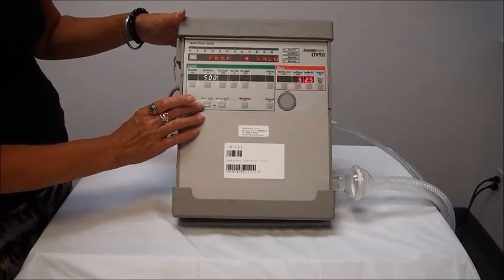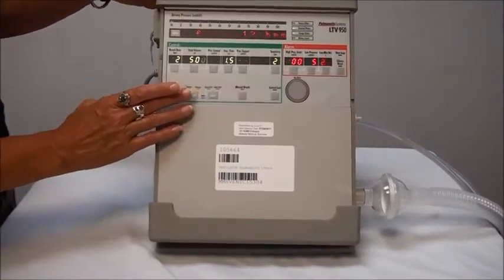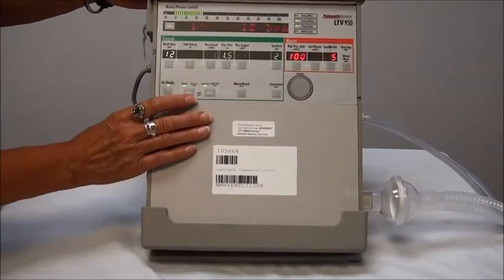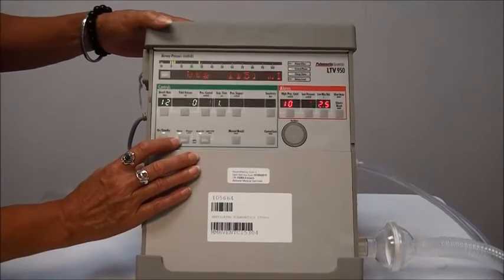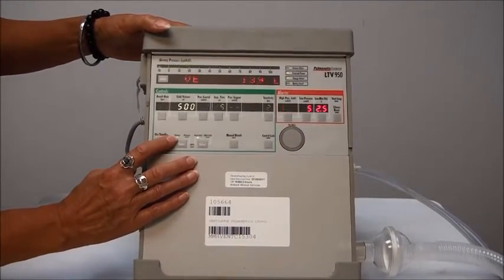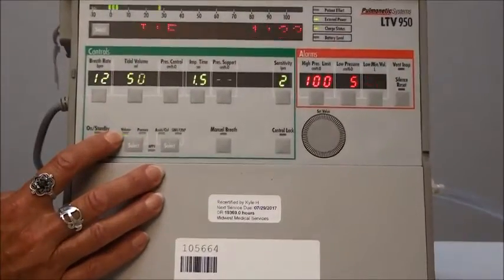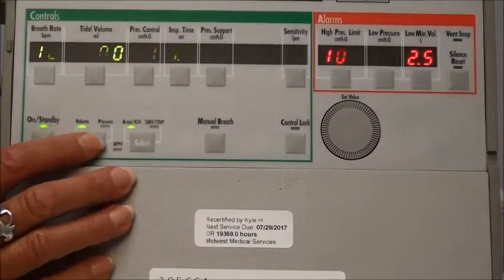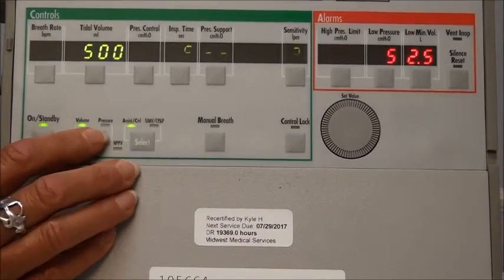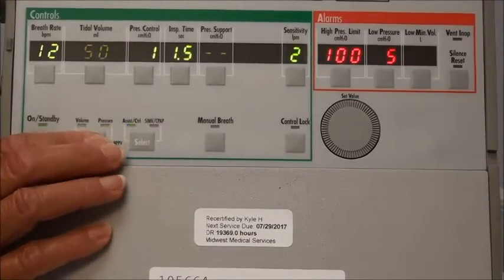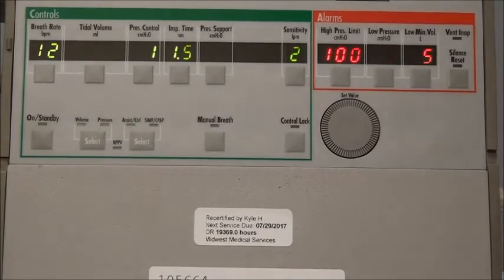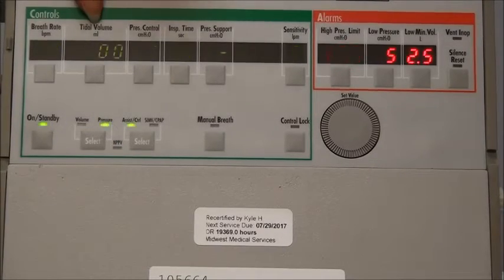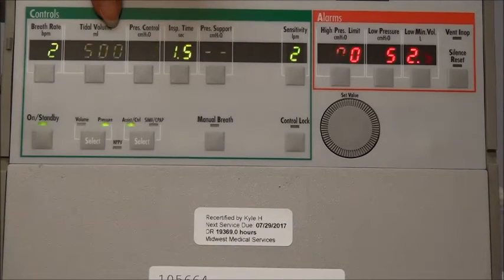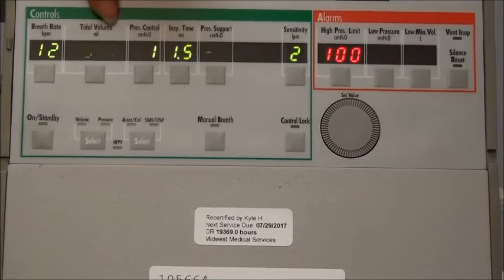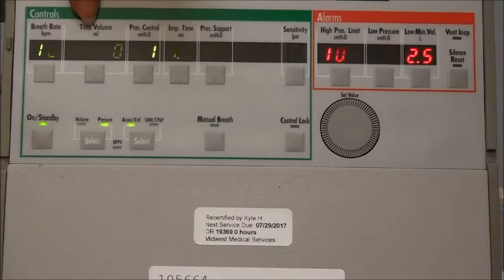Now if I change this to a different mode, you're going to notice some differences in the settings. So I'm going to go down, and there's the select button right below where it says volume and pressure. Right now you can see that the green light is lit up under volume. If I push that, the pressure light is going to be flashing, and if I push that again, it's going to change it. So now it's in a pressure mode. You'll notice that you no longer have a tidal volume showing because you don't put in a prescribed tidal volume in a pressure setting. You would put either pressure control or pressure support.